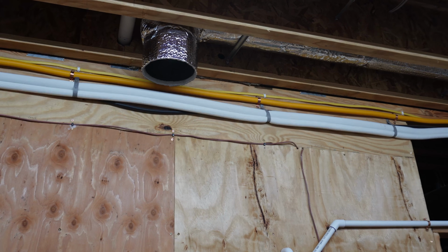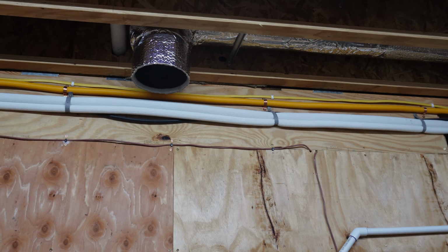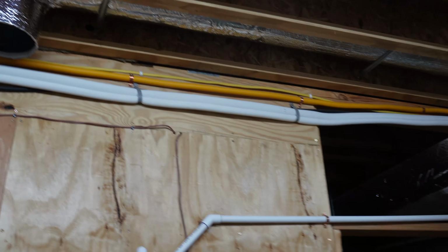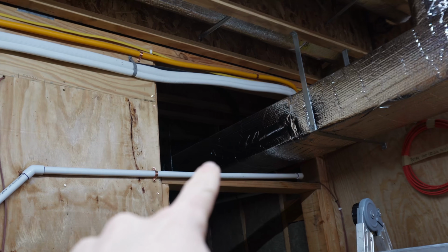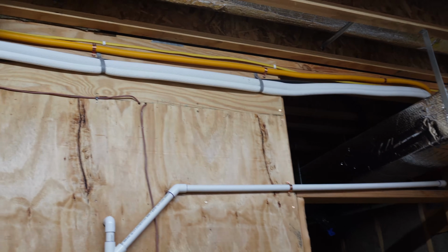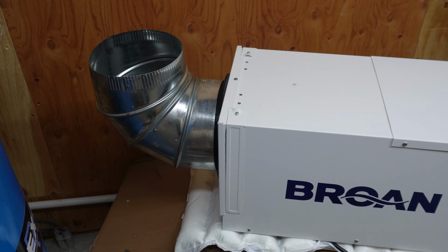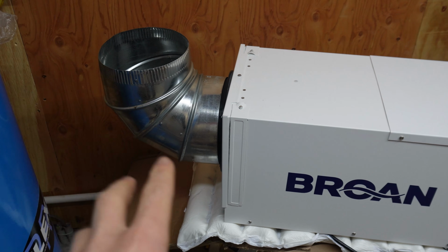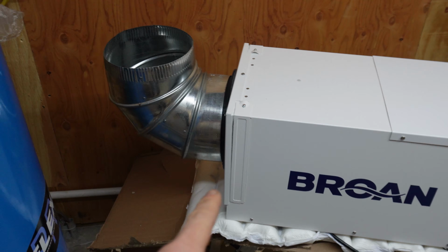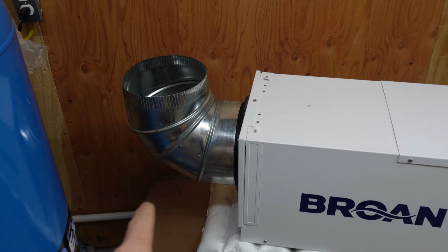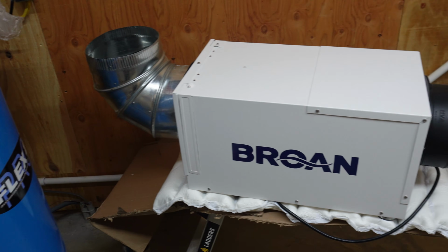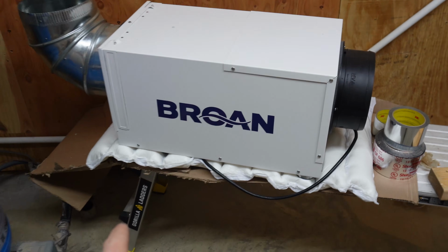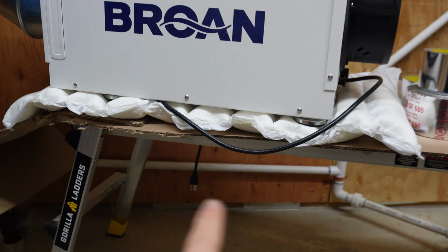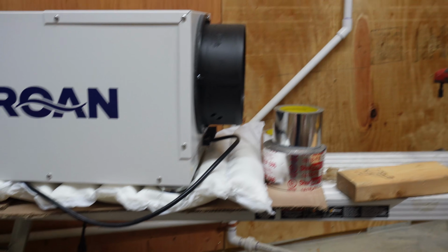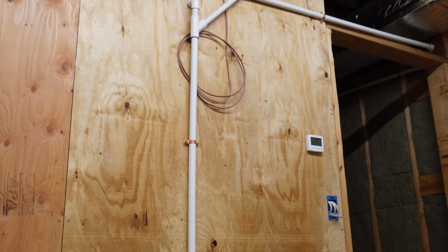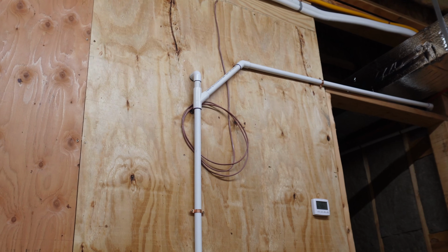I've done quite a bit of measuring of the unit relative to where this pipe is going to be and where our supply trunk is going to be, which is basically right next to the return trunk, so it's going to be mounted pretty high up on the wall. I'm using a rigid elbow on the end to turn the airflow down into the unit, and I'll use a very short piece of flex between that elbow and the stub coming out of the ceiling. With that elbow figured in and where the feet of this unit are, I've found I'll need to accommodate that condensate drain in my mounting platform.